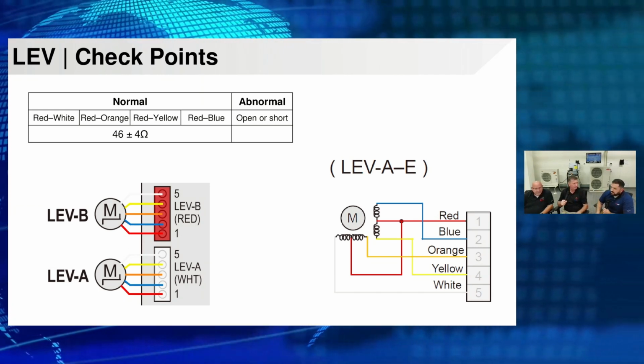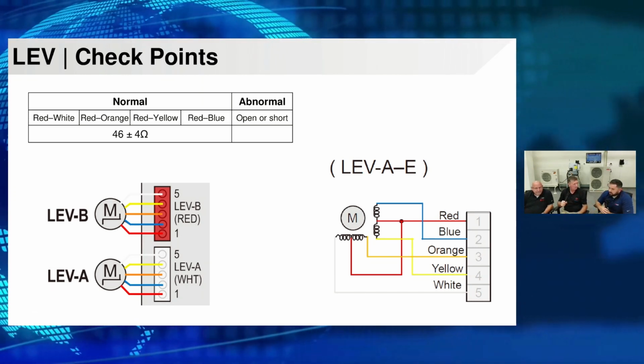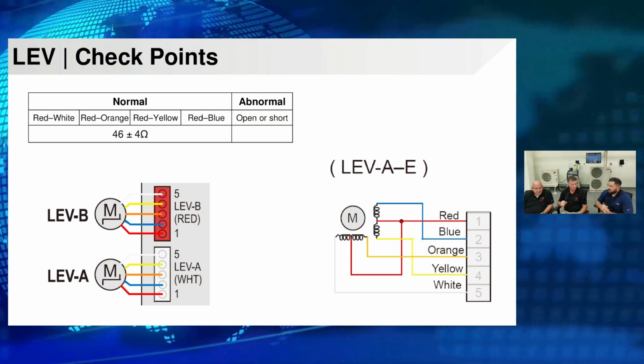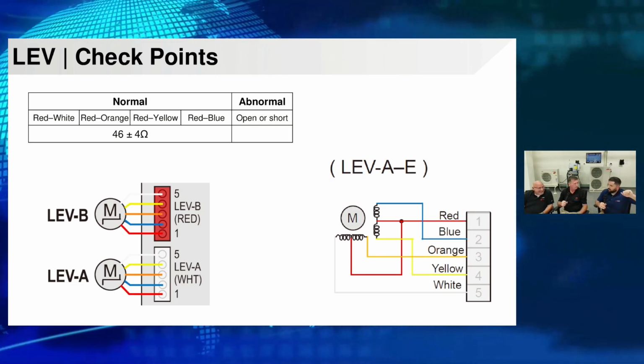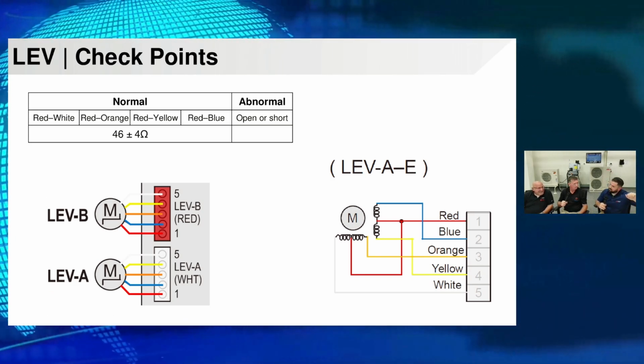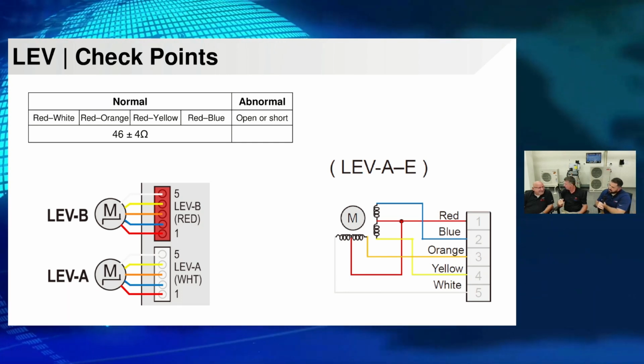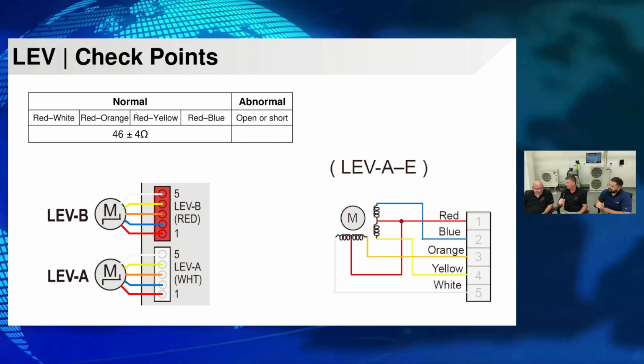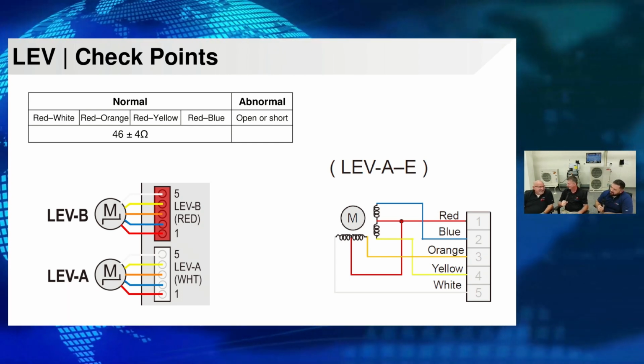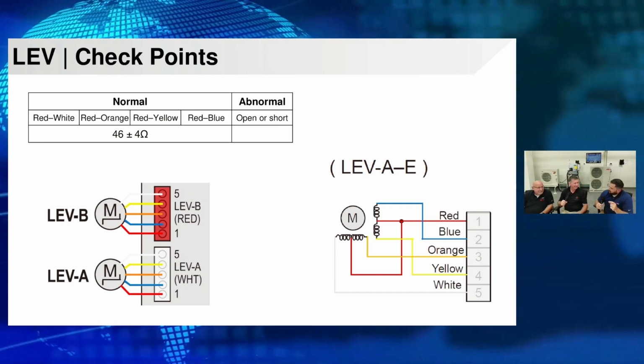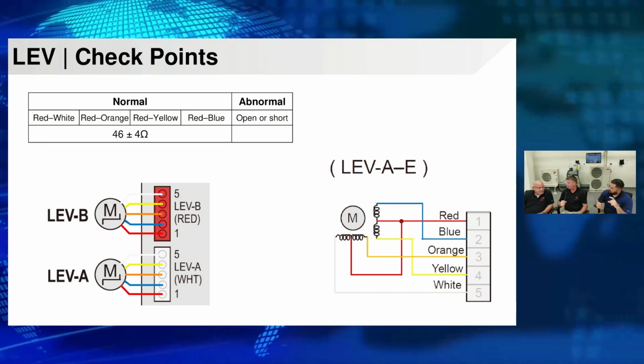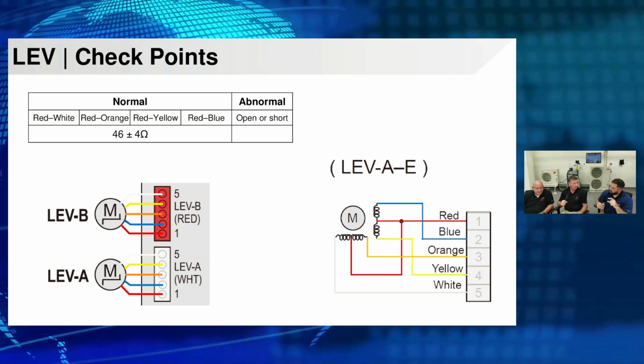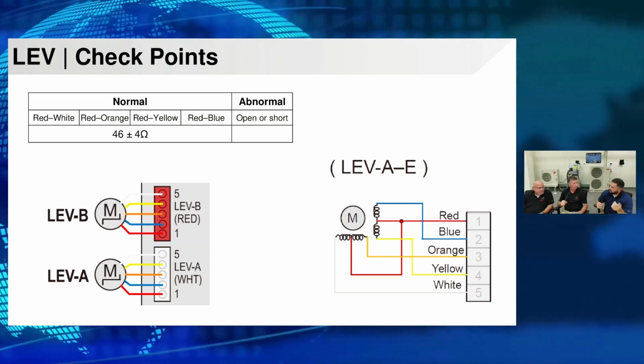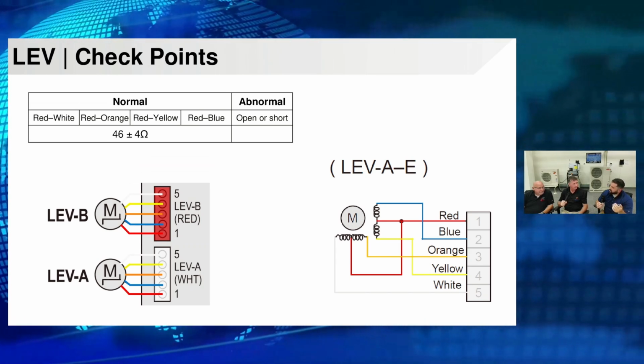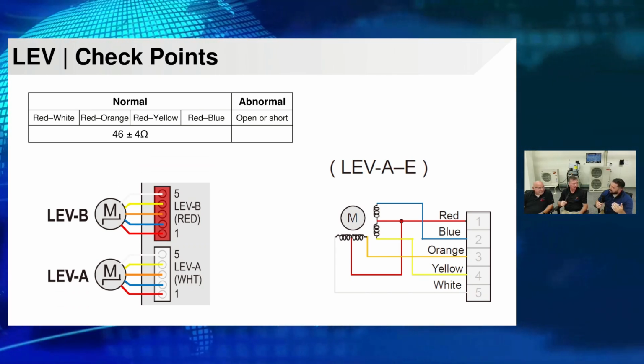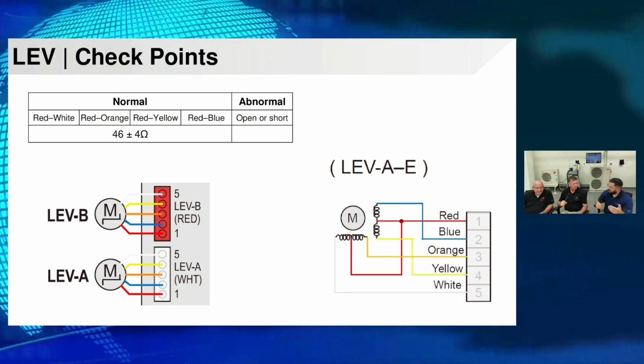So some of our LEVs on the residential side are about 500 pulse LEVs. But once you get into the commercial world, we have LEVs that are 3,000, 5,000, 6,000 pulse. Really? Oh, yeah. That's a lot. Well, it speaks to how much control you have over the refrigerant. Absolutely. It's any refrigerant management of an open to close. Fully open and fully closed is always going to be fully open to fully closed. If you have 5,000 steps to get there versus 500, the control that you have over the refrigerant is just drastically different.